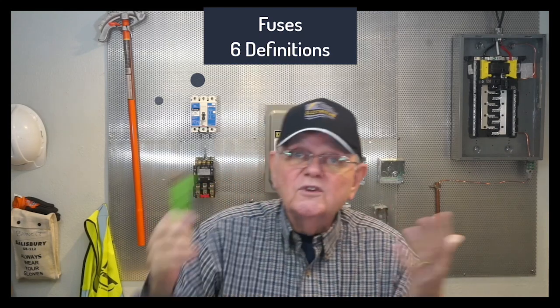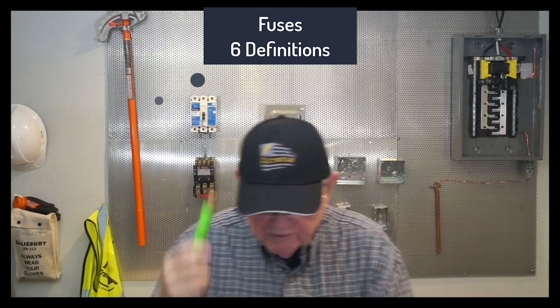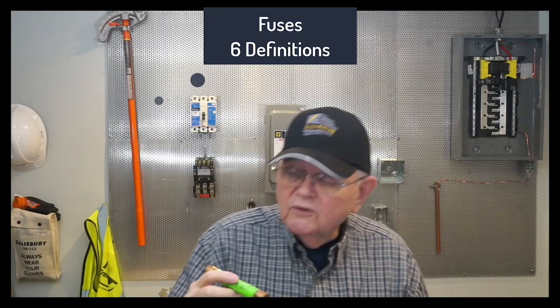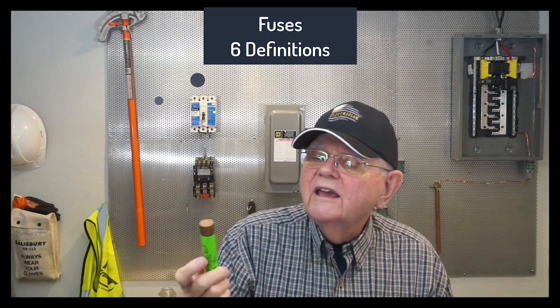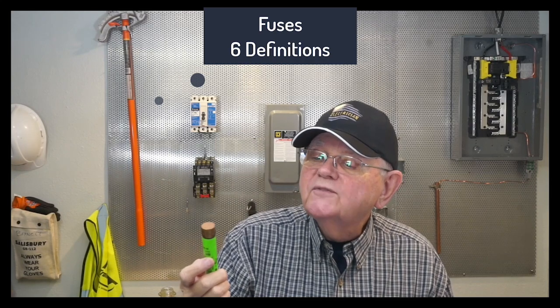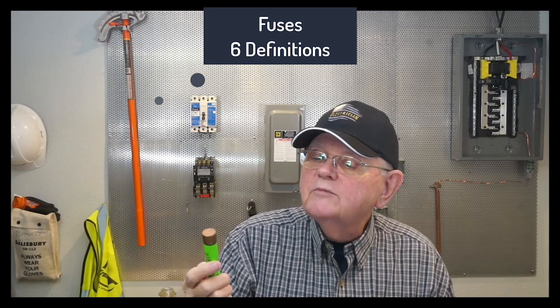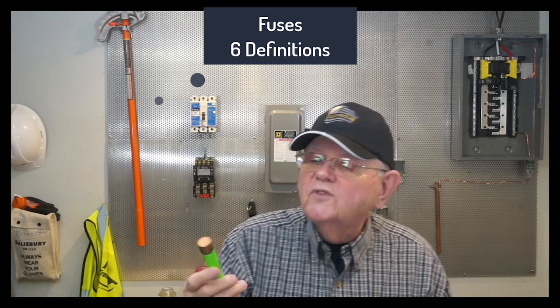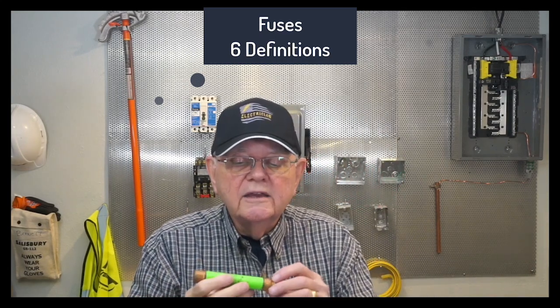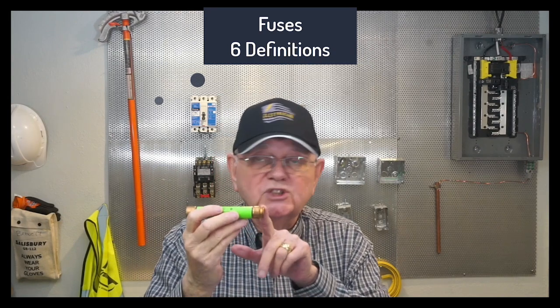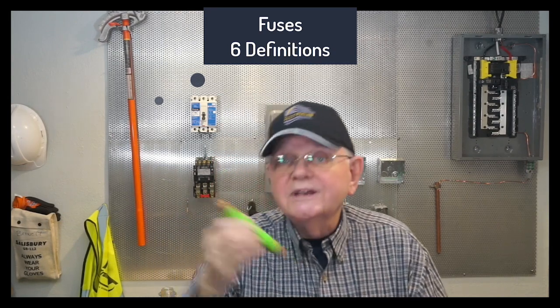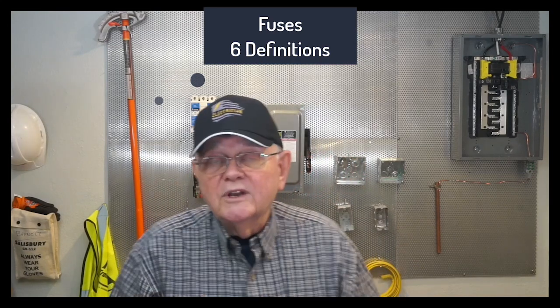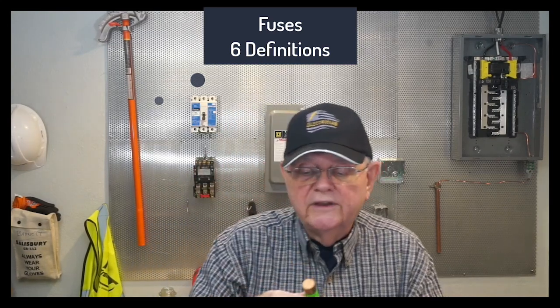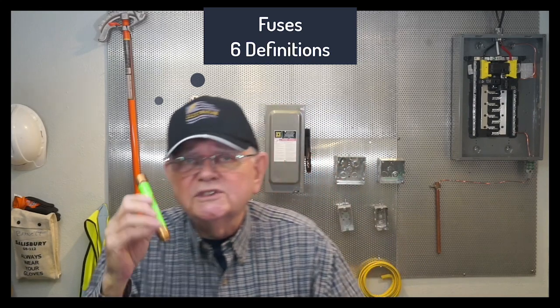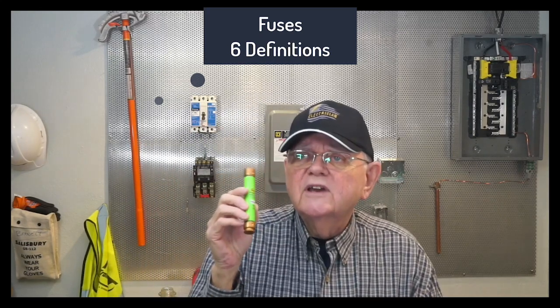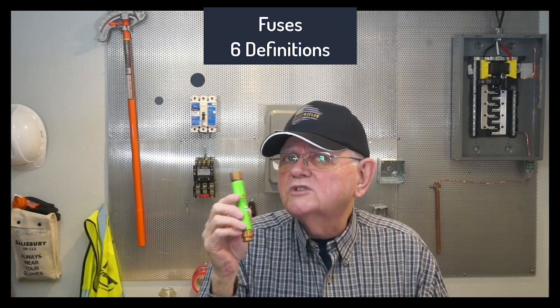I can have vented fuses or non-vented fuses. This particular fuse is a power fuse, right? And I take a look at it, and it's an energy efficient, dual element time delay class RK5 fuse. Well, the R in the classification tells me that it has a rejection feature on it, so I can only put it in a fuse clip that will allow this particular type of fuse to go in there. This is a 30 amp fuse. It's a time delay fuse. So what that tells me is I could use this on something like a motor or a transformer.